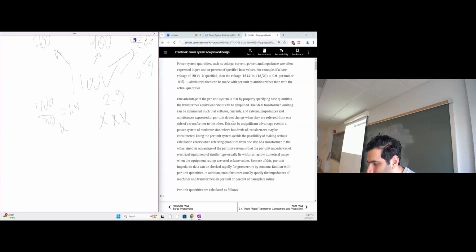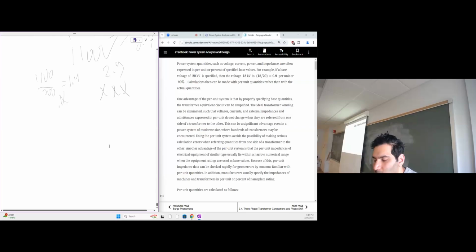This is one advantage. Second advantage, we'll get rid of referring. Whenever your system is running on the per unit system, you'll not be needing to refer anymore to the primary or to the secondary side. We've discussed those in the previous lecture. Okay, so we'll get rid of that problem. Actually, having one item to refer might cause us to make a number of calculations. But if I have 100 transformers, it will be very hard to make 100 or more referring for every component. So we get that issue solved also. So here you could read more about those advantages. I just summarized them for you.